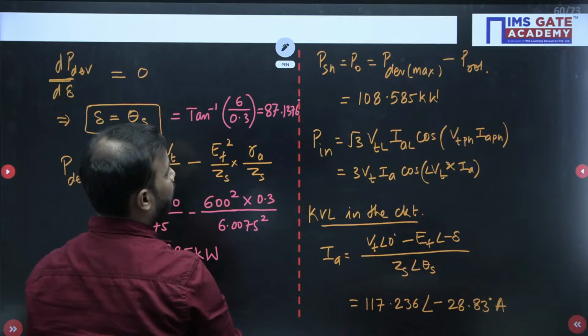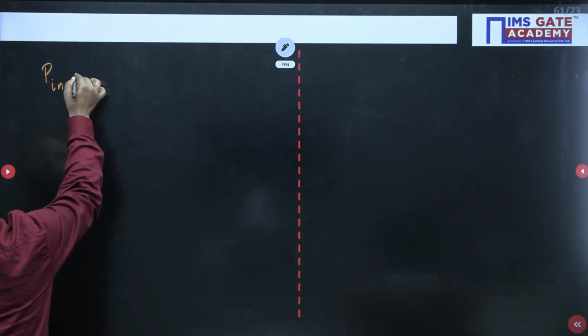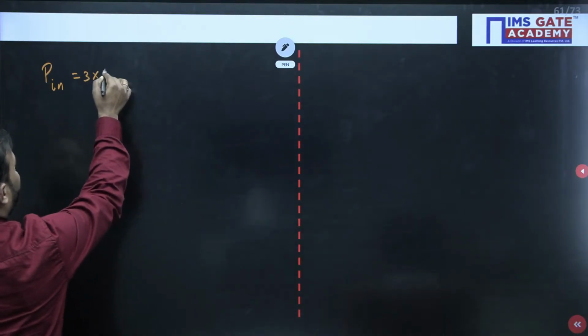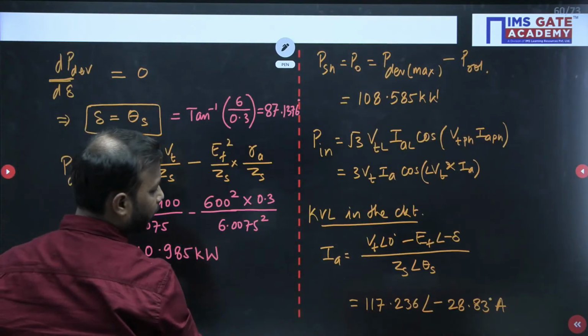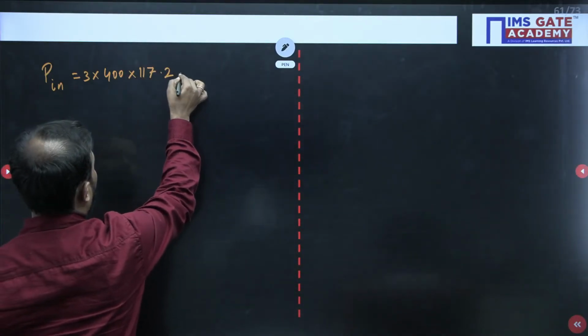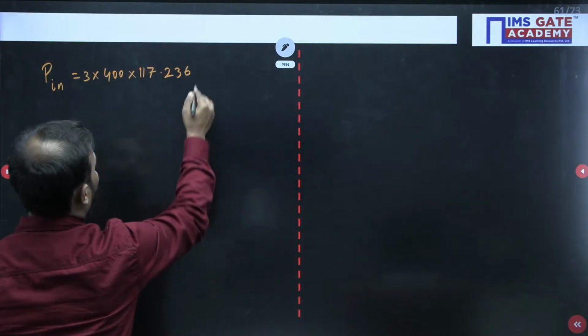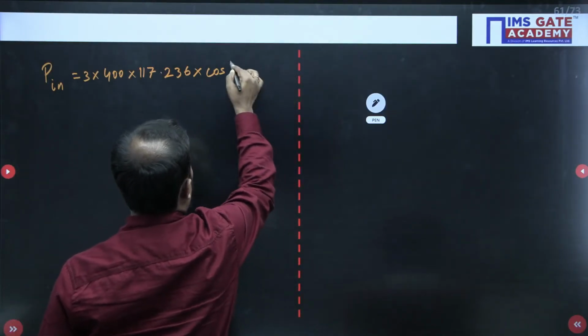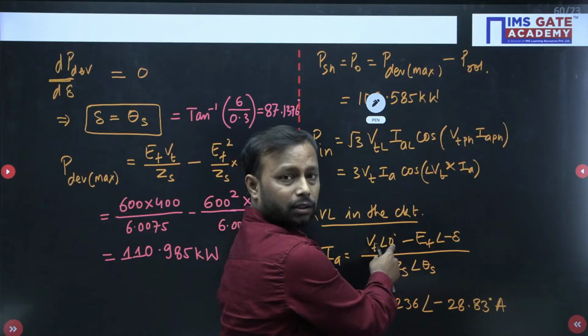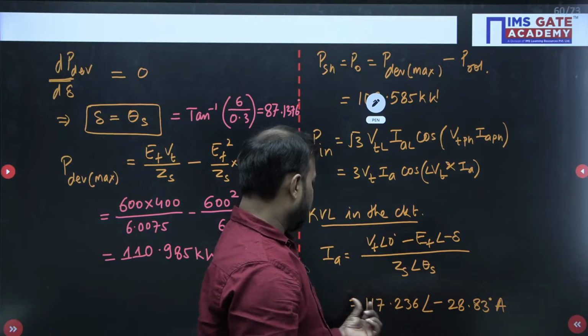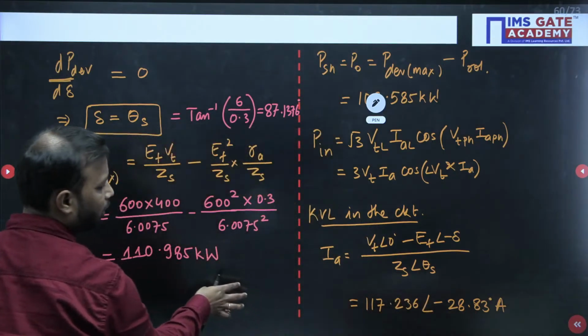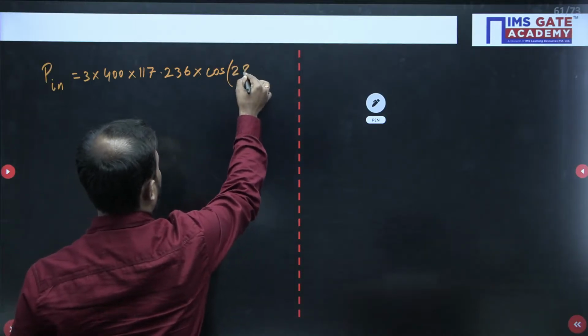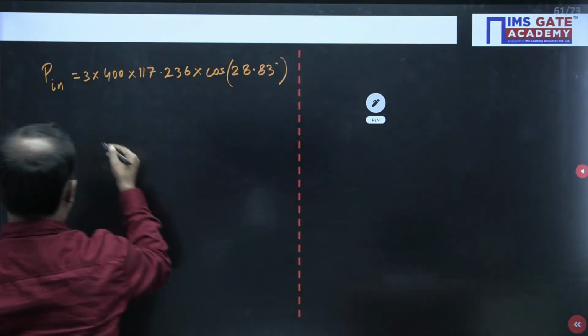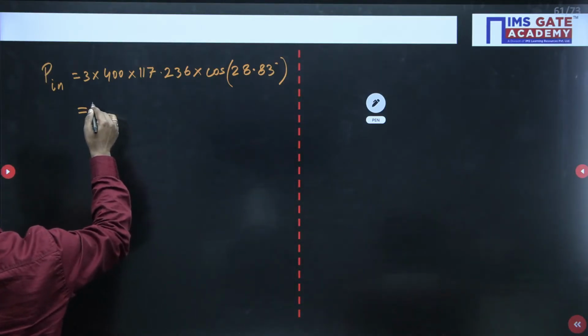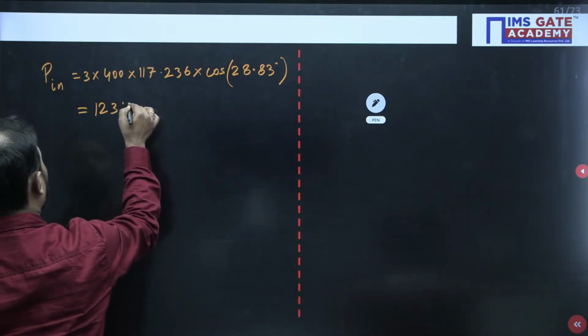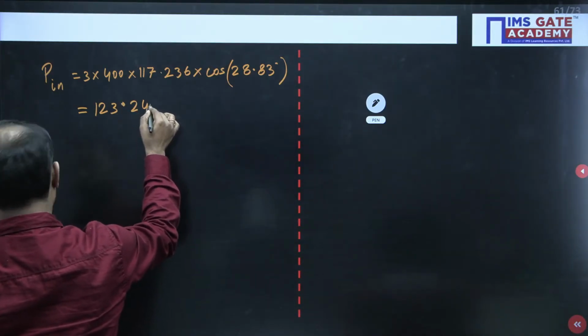Now in this equation, input power P_in equals 3 times the per-phase voltage (400) times the per-phase current (117.236) times cos of the angle between voltage and current. Since terminal voltage is the reference at 0 degrees and IA is at minus 28.83 degrees, the angle difference is 28.83 degrees. This gives an input power value of 123.2426 kilowatt.